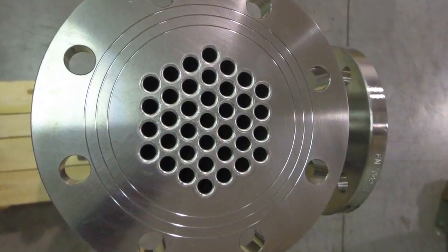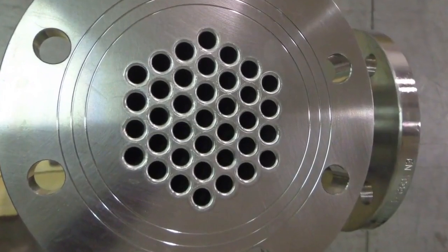Especially the two heads and the tubes. Why? Because combustion fumes, whether they are from diesel, biogas, or methane, can contain acidic elements that corrode the material of the heat exchanger, especially when operating at high temperatures. As a result, these heat exchangers are definitely made of stainless steel for the part in contact with the fumes. The outer part, or mantle, can be constructed using carbon steel.